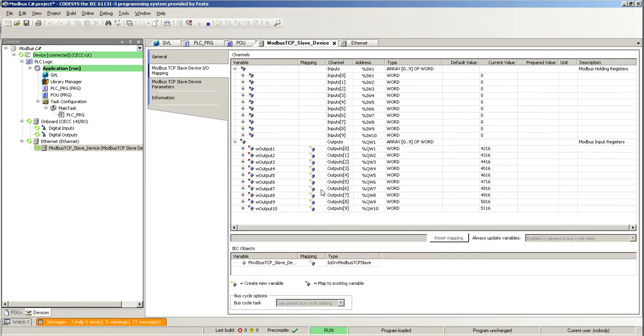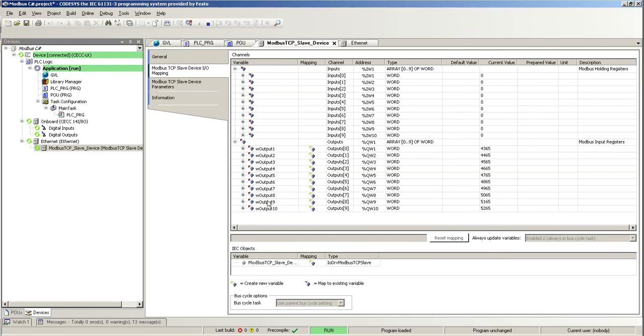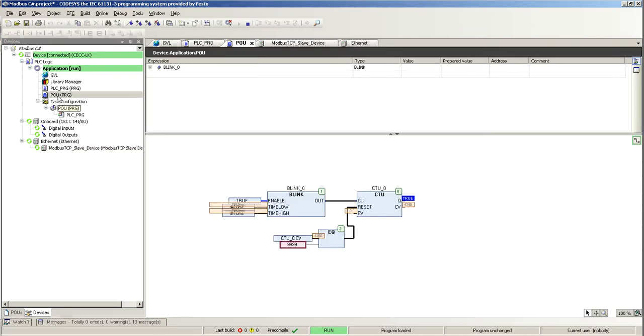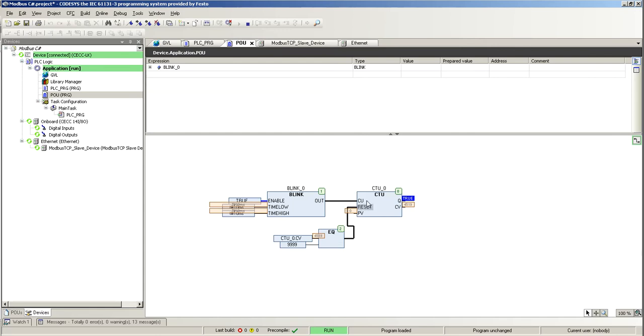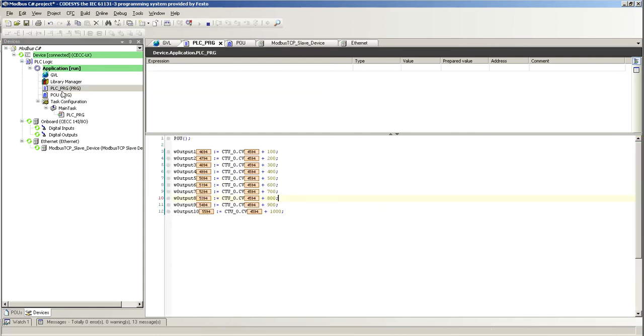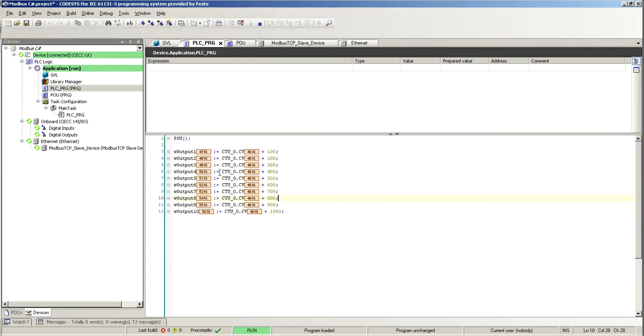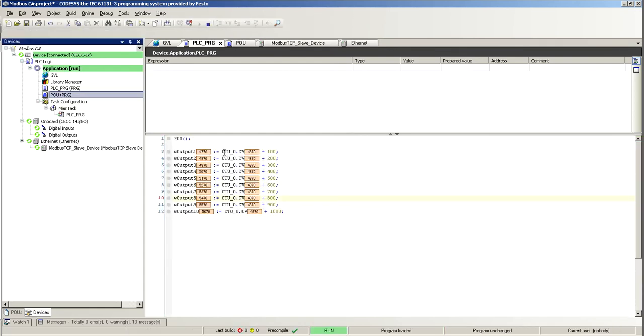So, basically, what I'm doing here is I'm running counters on different output addresses, and I'm doing that by just a blink block here, counter up, and then once I reach a set point, I just reset the counter. And here I call that POU, and I assign the values of the counter to my Modbus outputs.